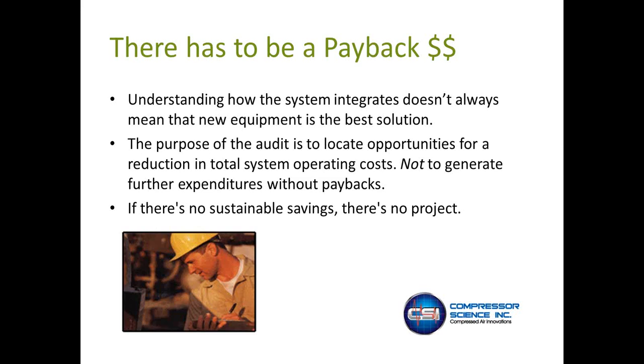A lot of people through the ERE program have put in variable speed drive compressors and have seen some savings, but if you're not resolving the issues out in the facility that are causing that compressor to stay loaded or to load unnecessarily, then there isn't going to be sustainable paybacks. So really the purpose of the audit should be looking for opportunities to reduce the total system operating cost, not to just look at buying new equipment, getting some rebate money and moving forward.